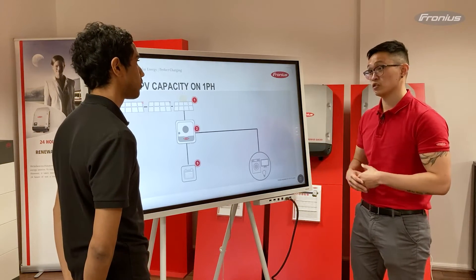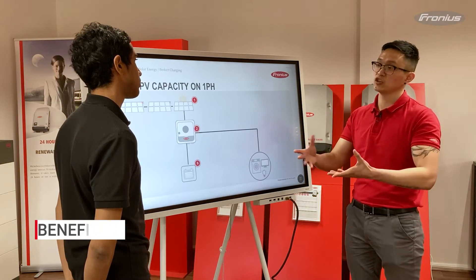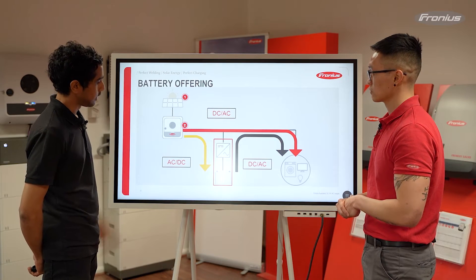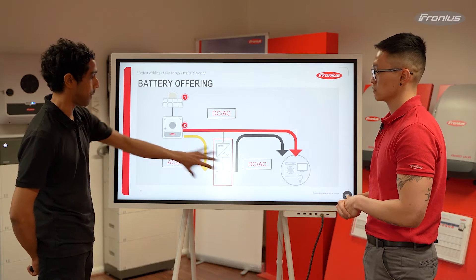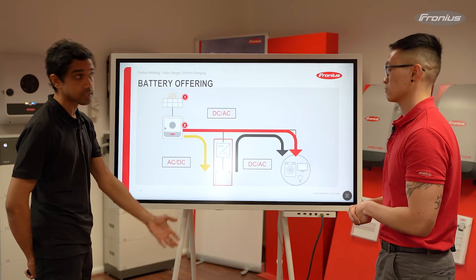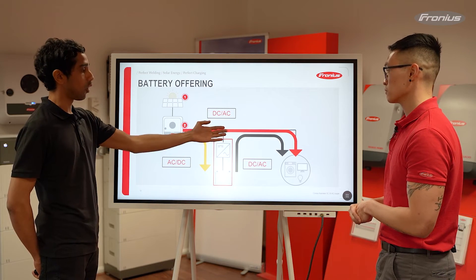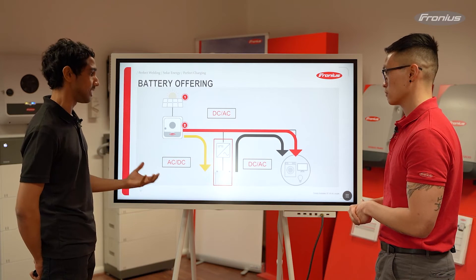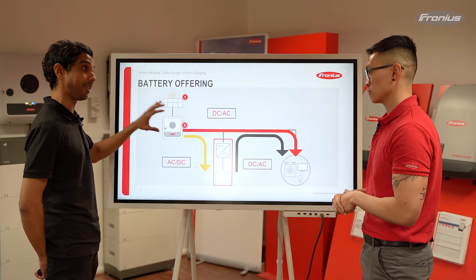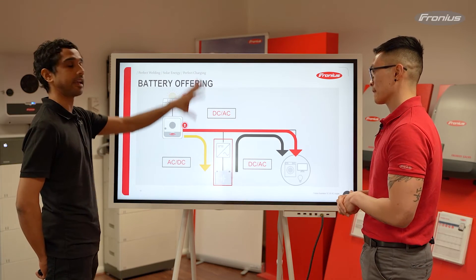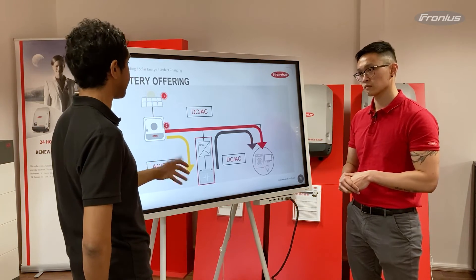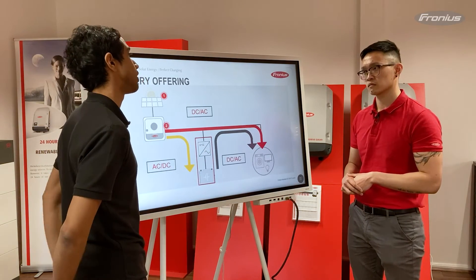Now for the benefits of an AC coupled solution. One of the main reasons someone might opt for an AC coupled solution is that, because the battery is attached to the AC side of the system rather than directly to the inverter, you can retrofit it onto pretty much any system — whether it's a new system or an older one, you simply link it onto the AC side. With a DC coupled battery, you need a hybrid inverter that can accept DC coupled batteries, and you also have to ensure compatibility between the inverter and the battery. Additionally, some customers may prefer a particular feature, monitoring platform, or other aspect of a specific AC coupled battery.